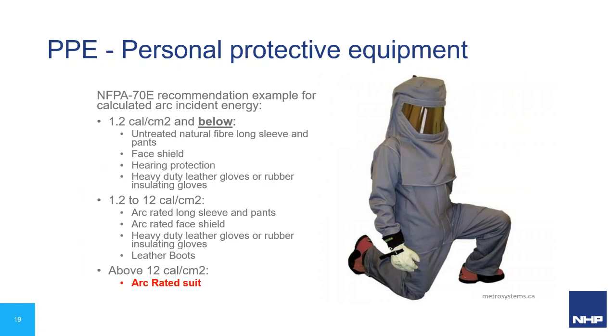So looking at that PPE recommendation. This is for the calculated arc incident energy that we saw earlier. So 1.2 calories per centimeter squared and below. This is basically from nothing up to a fairly low figure. So untreated natural fiber, long sleeves, pants, a face shield, hearing protection, heavy duty gloves. It's talking about this for anything basically that you go work on.